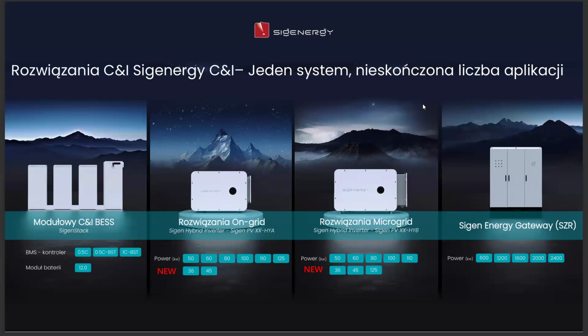1C performance and EV charging, a major economic advantage. The 1C standard is also extremely important in electromobility applications. Imagine the following situation. An EV arrives at a company site and is connected to a charger. In a fraction of a second, a very high power demand spike appears. For many systems on the market, this is a problem because they operate only at 0.5C. With our 1C capable system, that peak is handled immediately, without overloading the grid connection and without the risk of penalties. And this leads directly to a key economic advantage.